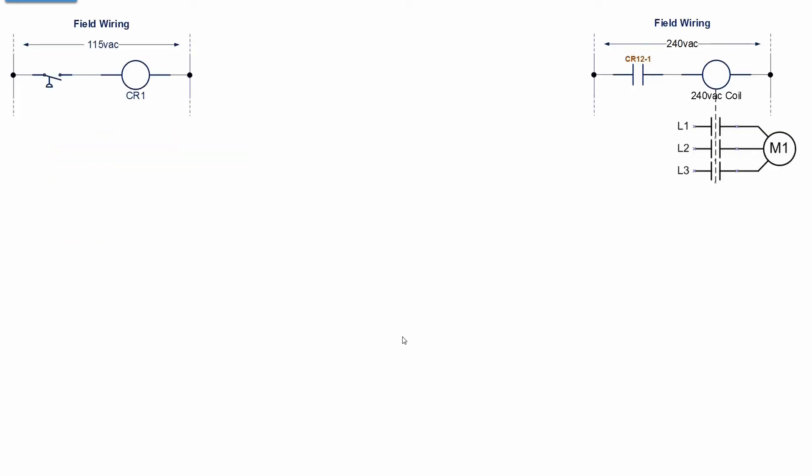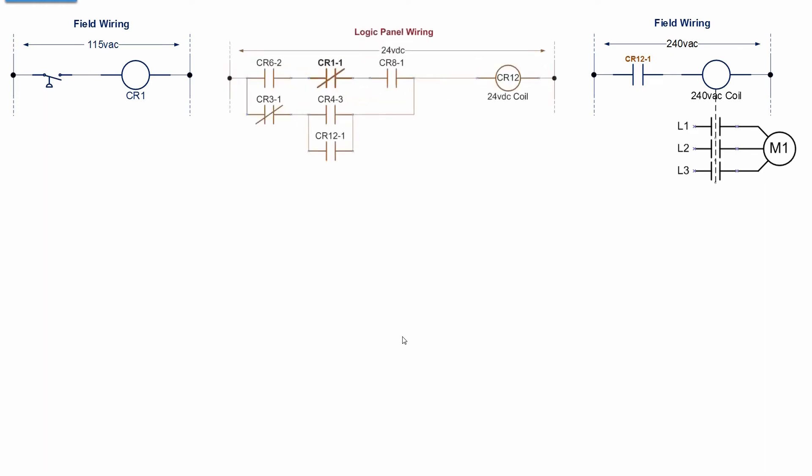Let's take another example. Here's our field wiring — we have a pressure switch that operates on 115 volts AC in the field. It energizes control relay CR1. On the output side of the field wiring we have 240 volts AC. There's a relay CR12 that will control a contact, and when that contact closes it will energize a coil and close three contacts that supply three-phase power to the motor. Here's the logic for relay CR12. We don't see the coils here — we're just grabbing one chunk of relay logic: one field device, which is CR1, the pressure switch on the hydraulic reservoir. That pressure switch closes when the hydraulic pressure is up to the set point, and when we close contact CR12 that runs the motor to pump the pressure up. That is a rung of ladder logic.